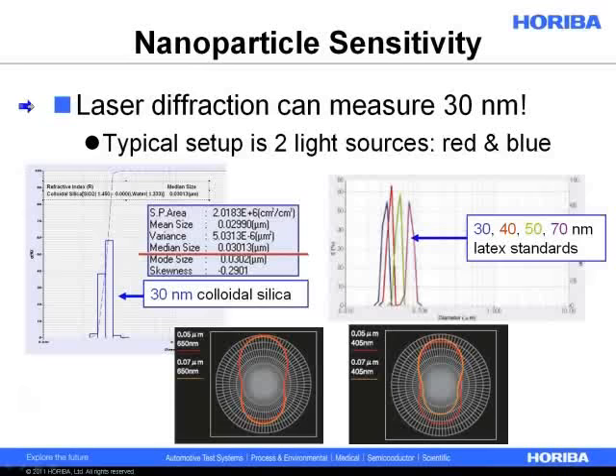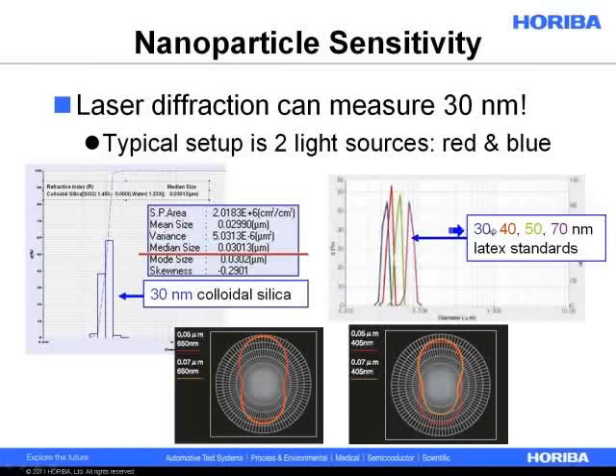Diffraction has been proven to have very good sensitivity to nanoparticles. The Horiba LA-950 is still the only analyzer that can measure down to 30 nanometers, using a red and blue light source setup. We measured colloidal silica — Ludox TM — and it came in at a median size of around 30 nanometers, which is fairly close to what is on the bottle. We can also measure polystyrene latex size standards at 40, 50, and 70 nanometers, and it can distinguish between them. It has decent resolution underneath 100 nanometers, though not as good as the resolution above a few hundred nanometers.